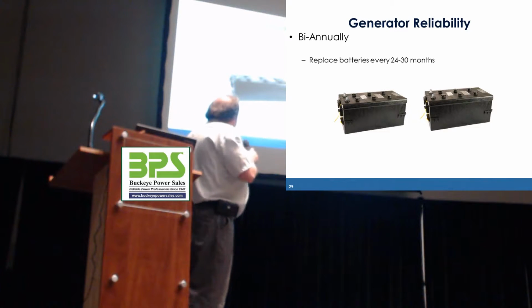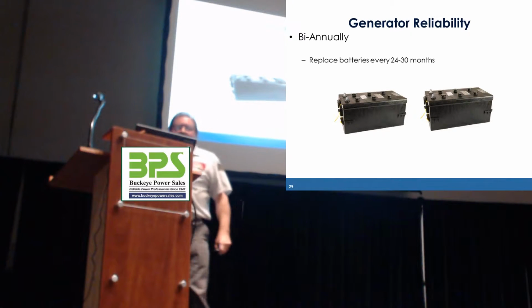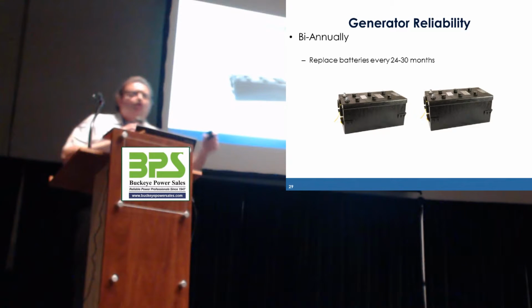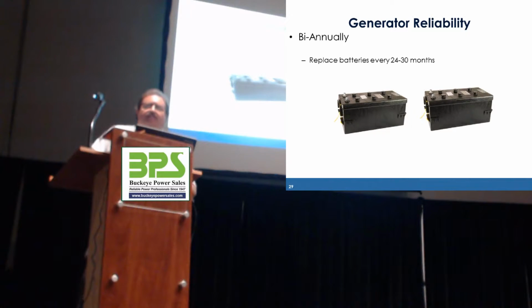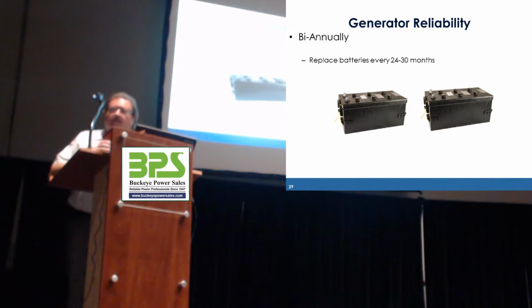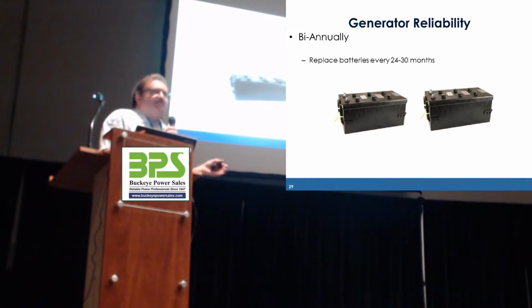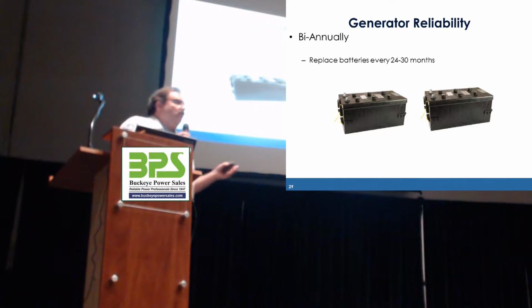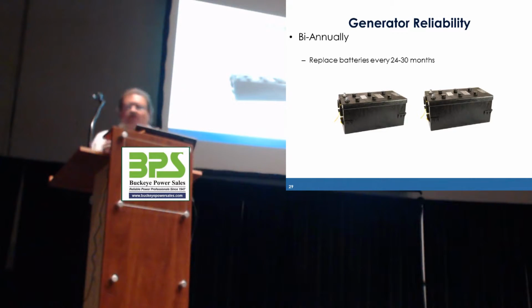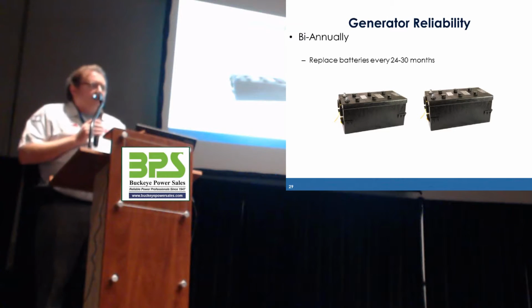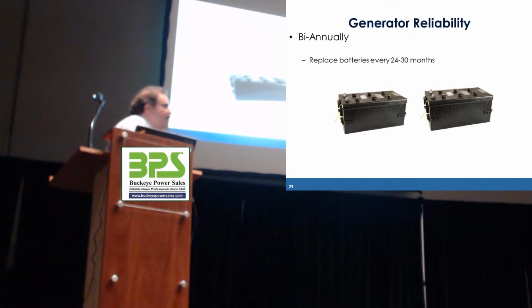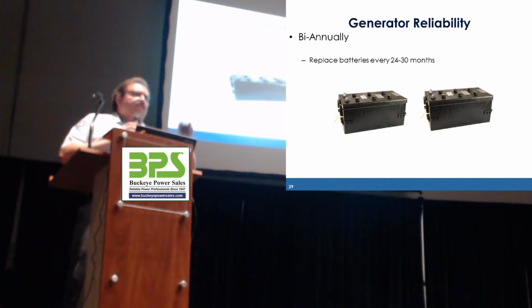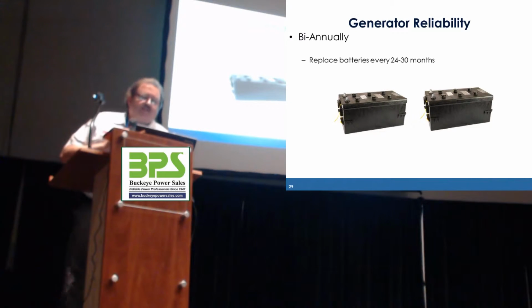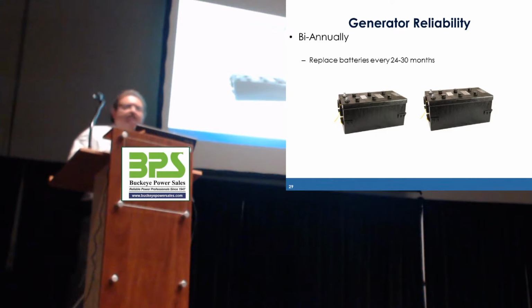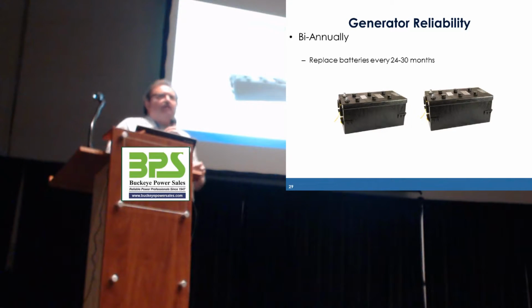So this is a should. NFPA 110 says that your batteries should be replaced every 24 to 30 months. Okay? We've discussed it's the weakest link, even though I know that you're checking those batteries monthly and making sure that they're maintained. The battery in your car is warranted for 5 years or 7 years. Why should I put out the money for a new set of batteries every 2 years?